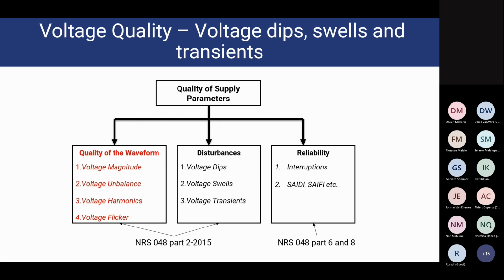So this is the first leg which falls under the quality of supply banner. As I said, we already covered disturbances, which are voltage dips, swells, and transients. And today the focus will be on quality of a waveform. So how do you define the quality of a voltage waveform? Using specific parameters such as the voltage magnitude, unbalance, harmonics, and flicker. Now, the NRS 048 Part 2 is the standard that we'll mostly be referring to in the training today. That's the standard that we use in South Africa that defines the compatibility levels or limits that are used to compare your voltage quality with the limits defined in that standard.